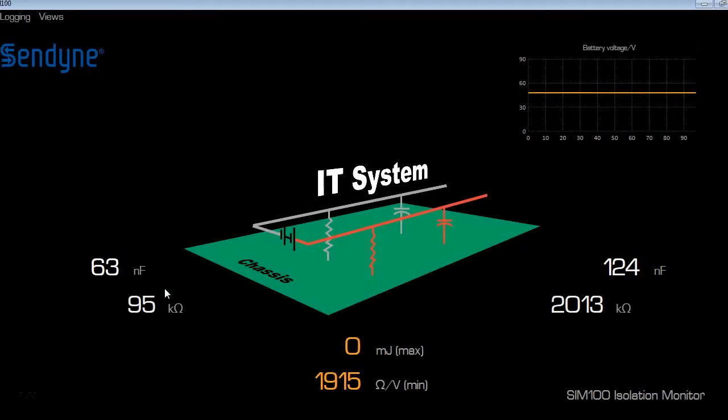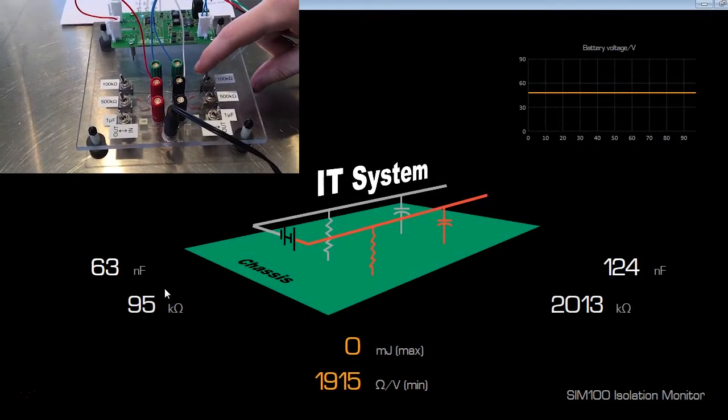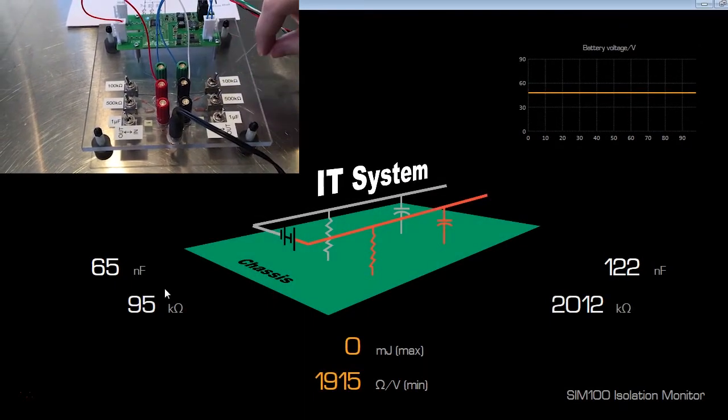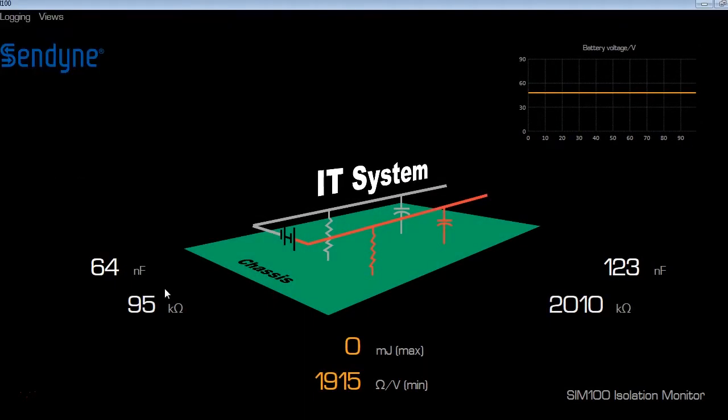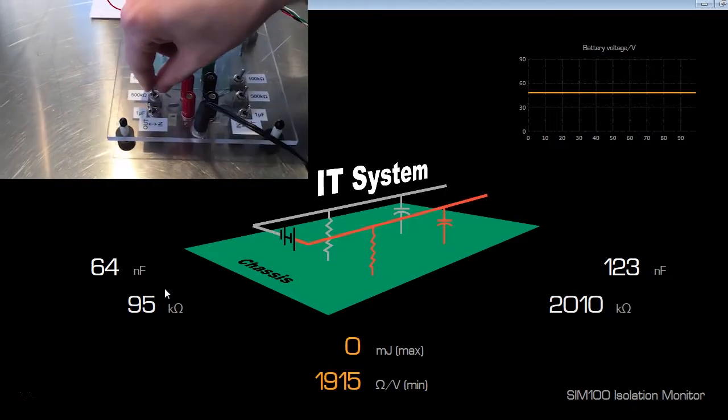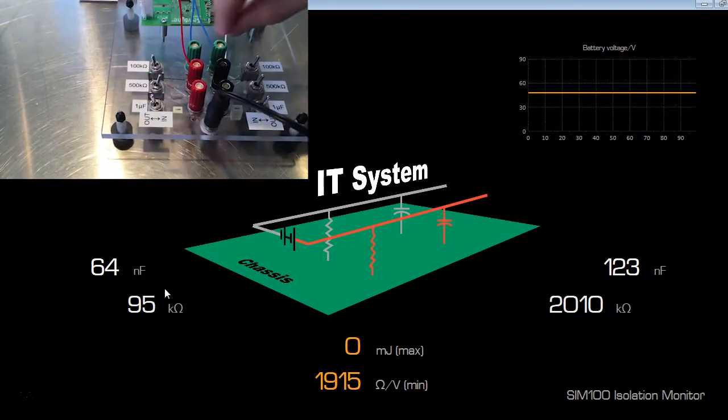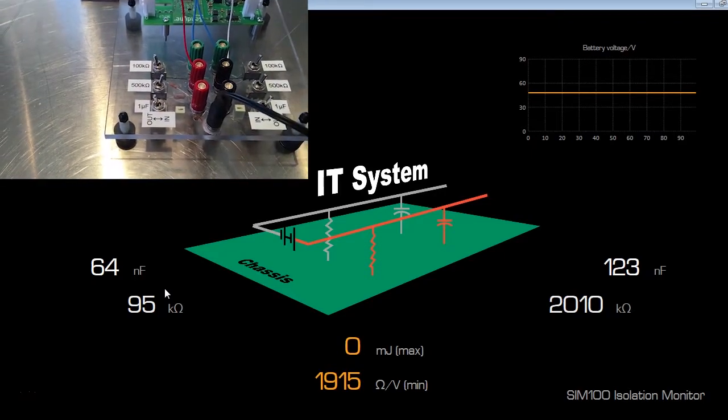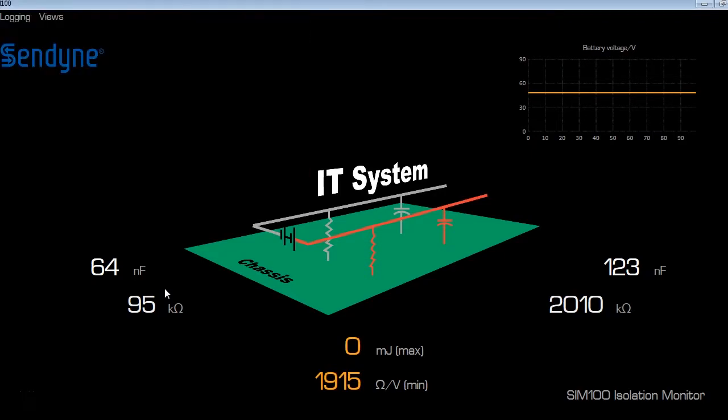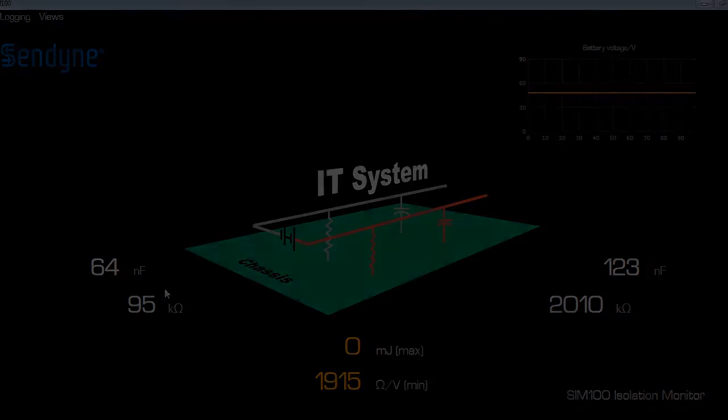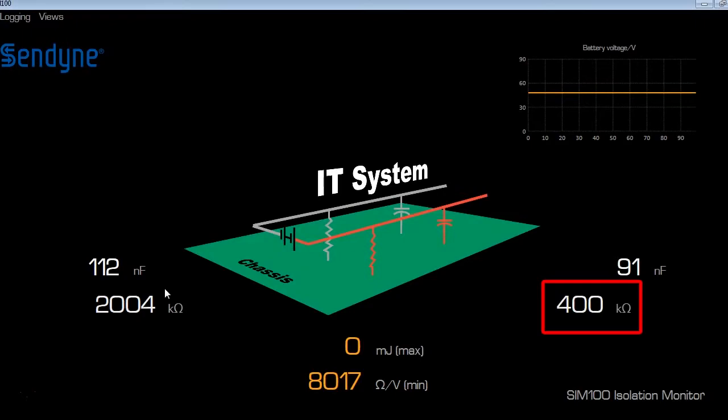Now I will remove the 100 kiloohms and add in 500 kiloohms on the positive end of the battery. Now I wait for the SIM100 module to recognize the change in the circuit. Once it does, then the leakage resistance should say 400 kiloohms on the positive end of the battery.